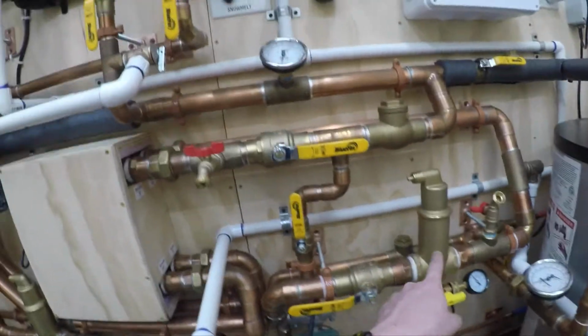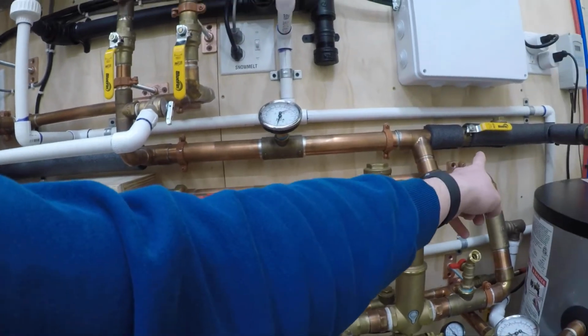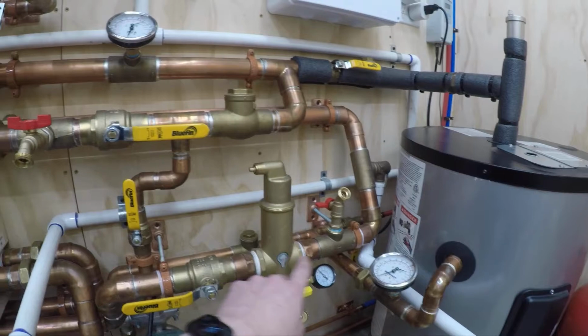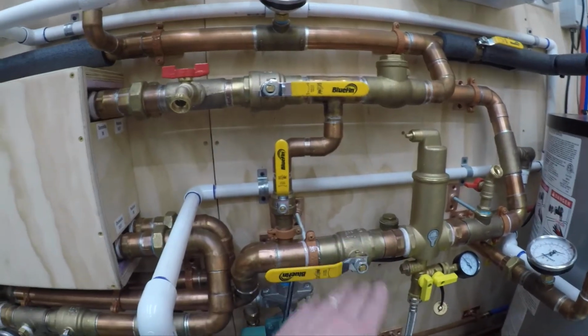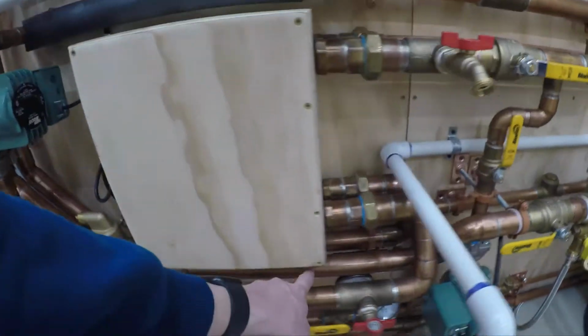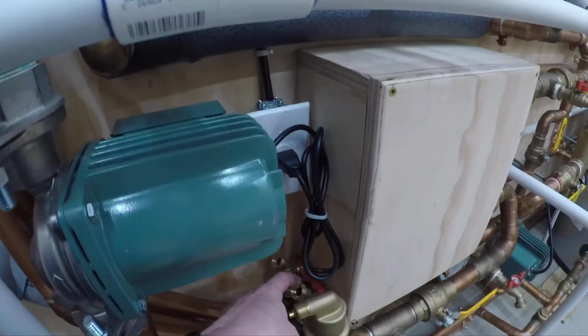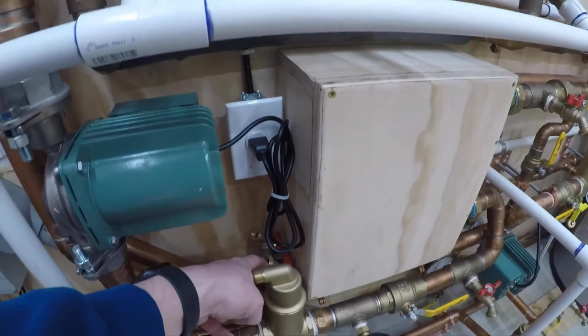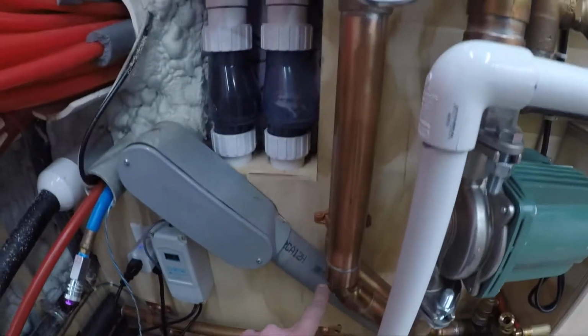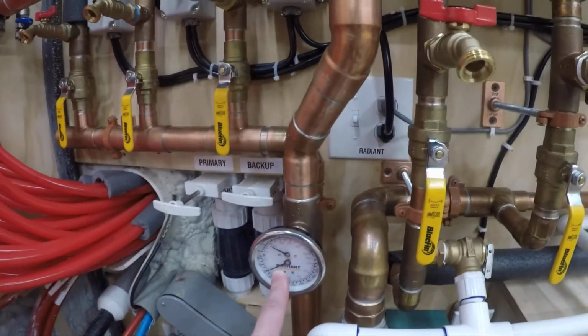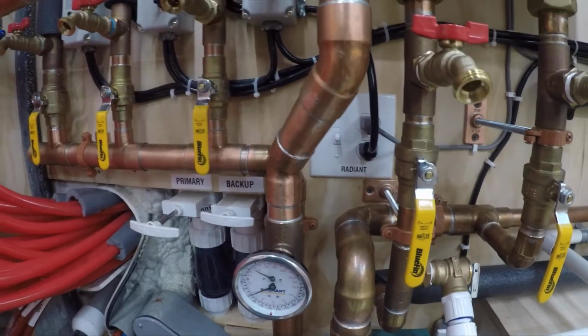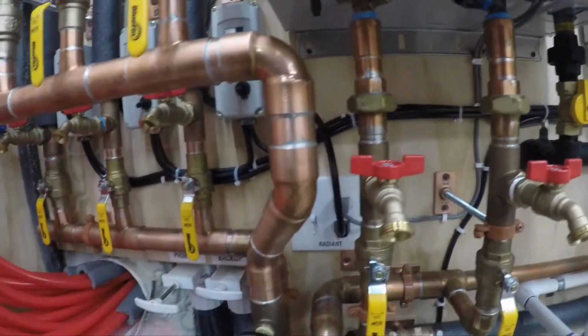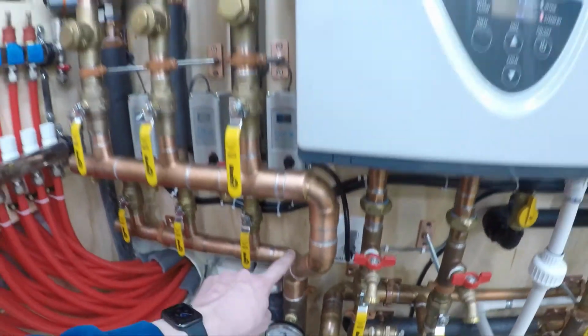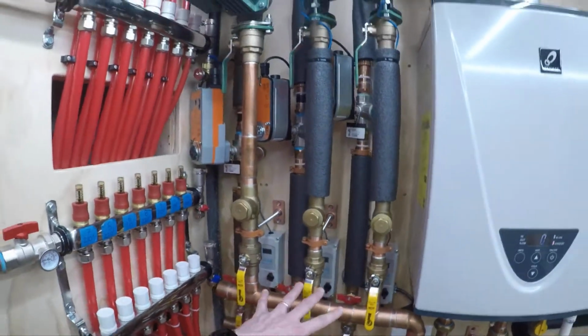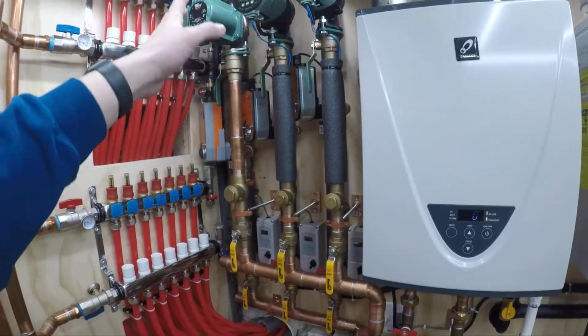So anyway, that primary loop comes out with heated glycol, comes around, goes through the bubbler, shut off valve, comes down underneath here in the front to another fill valve, which I use exclusively too. Up here in the front, I have pressure and temperature so I can see what temperature I'm getting to my zones right here. Comes up and then it goes out to each zone.